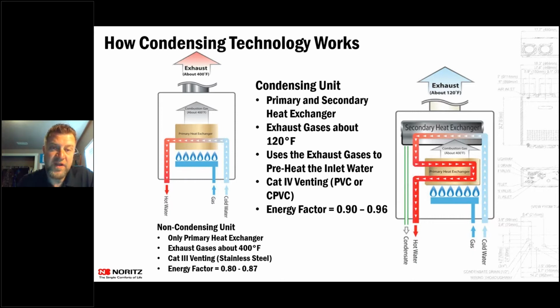So like we have UEF ratings on some of our units up to 0.97. UEF ratings, which the energy factor would be like a 0.98 or a 0.99, but we don't deal with energy factors anymore. There's still a bunch of different municipalities that I see around the nation that in their code books are still referencing energy factor, which will be changing here as those code books update over the next few years. But UEF is what everything's going off of right now. So any questions on condensing versus non-condensing right now?